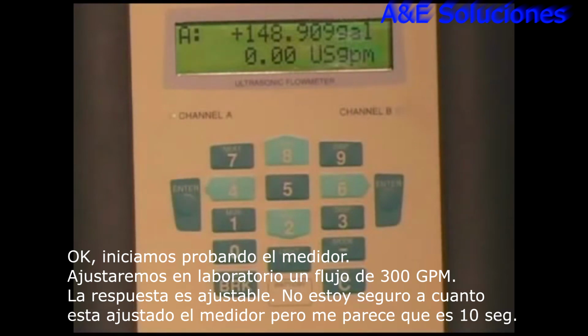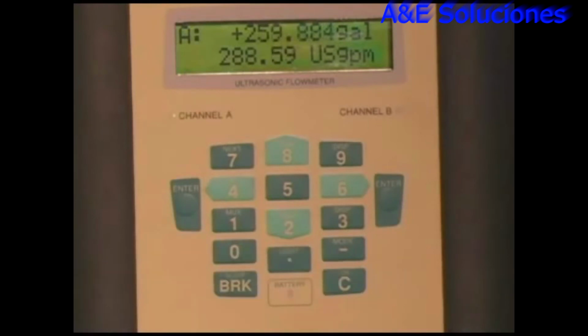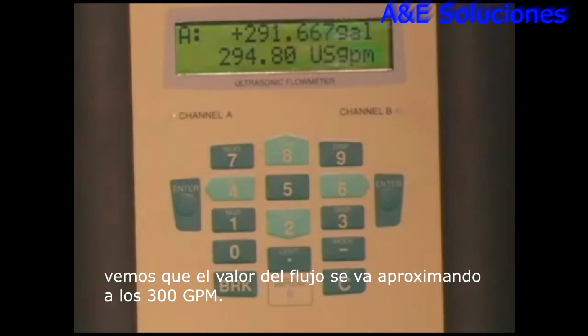Okay, I'm going to start up the flow now. This is the Flexim calibration lab that we're working in, and I'm going to dial in a flow of 300 gallons per minute. Now, the response that you see is settable. The meter has a default. Not sure what this meter is set at right now. Looked like it had about a 10-second response set in. You'll see that the flow is starting to settle into the setting that I set the CalLab for, which is 300 GPM.